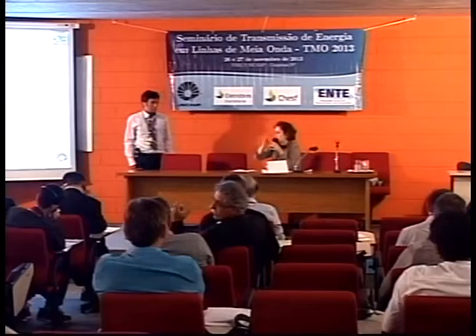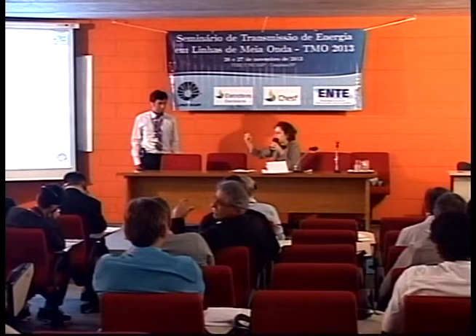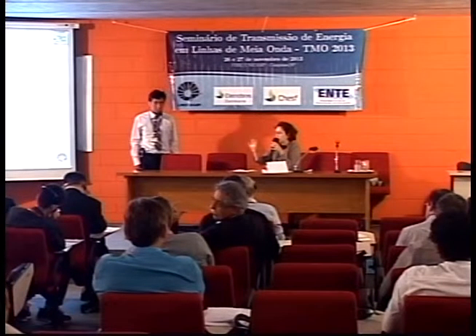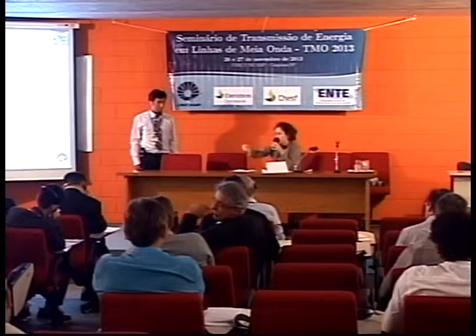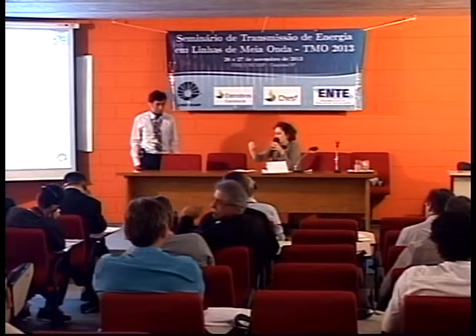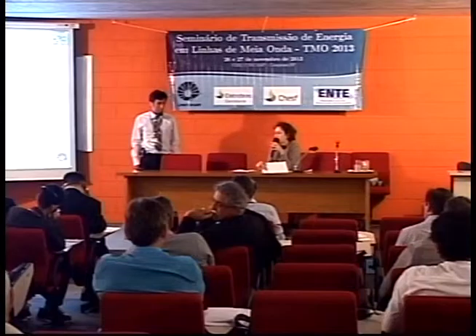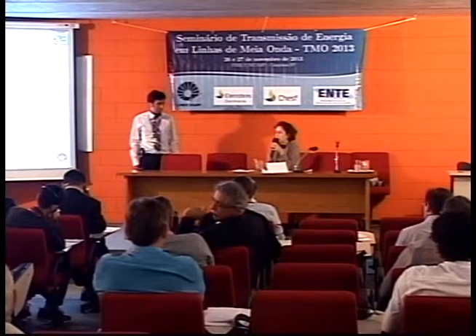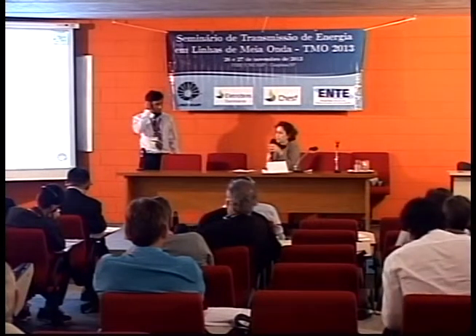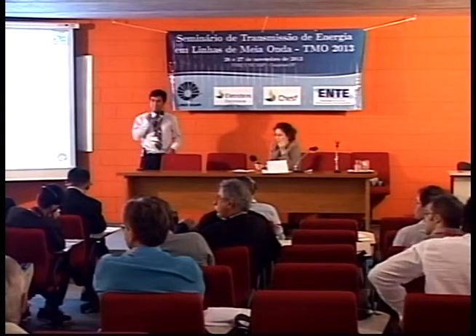I do not agree with what you say that the surge arresters are hindering, that are absorbing. This is not true. What we can monitor during the test, the energy in the surge arrester, what actuated, what didn't, and then we do the math backwards.